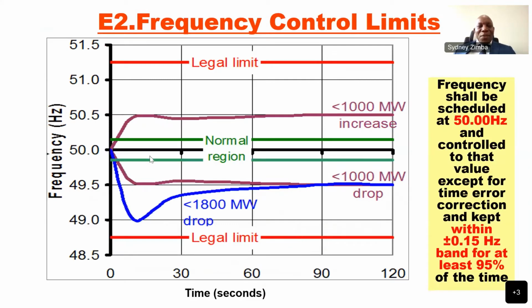If they don't balance, your frequency will be lower. The green lines you see here, this is the normal band. Our frequency is expected to be within this band. If there is a sudden change, loss of our biggest contingency, which is a generator of capacity 930 megawatts, nuclear power plant in South Africa. Studies have shown that we can only dip up to this point, 49.5. Or if we've lost an equivalent load, the frequency can shoot up to 50.5. Multiple contingency, loss of the HVDC input from Mozambique to South Africa, about 1,800 megawatts, we can drop up to this level. That's how our system has been tuned.